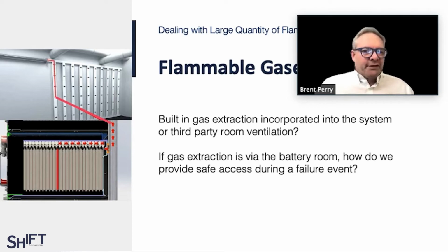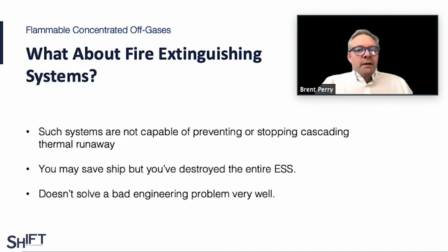Or do you have a way of extracting and managing that gas unique to the environment that the battery is in, so the gas can be safely managed, extracted, measured, even burned in a burning box before it gets exposed to anything? This way you can naturally disperse the gas to a much larger volume environment other than something like a container. And if you can do this, you can effectively make the battery room a safe place to operate and work in, even if you are seeing a battery failure.